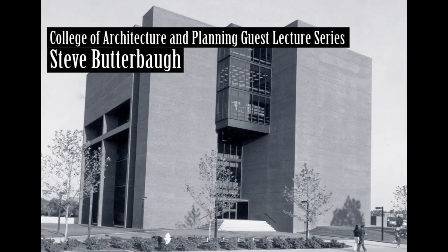What is the most to least operating cost savings? In the Army's case, once more, the lights came in first again with a savings of $9,388 per year. The emergency air handler moved up to second with a savings of $4,143 per year. The surgery air handler moved to third with $3,474 per year, and the windows came in last with $229 per year.